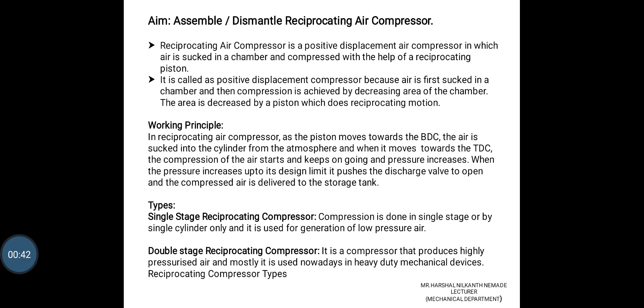Working Principle: In the reciprocating air compressor, as the piston moves towards the BDC, the air is sucked into the cylinder from the atmosphere. When the piston moves towards the TDC, the compression of the air starts and keeps going, with the pressure increasing. When the pressure increases up to the design limit, it pushes the discharge valve to open and the compressed air is delivered to the storage tank.